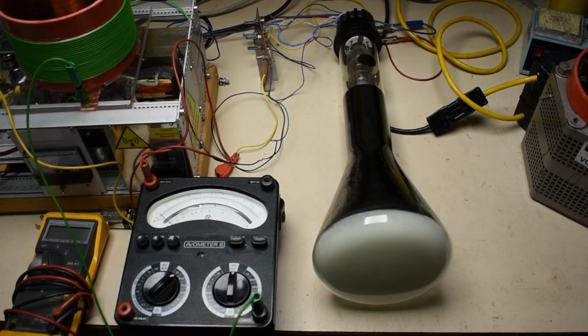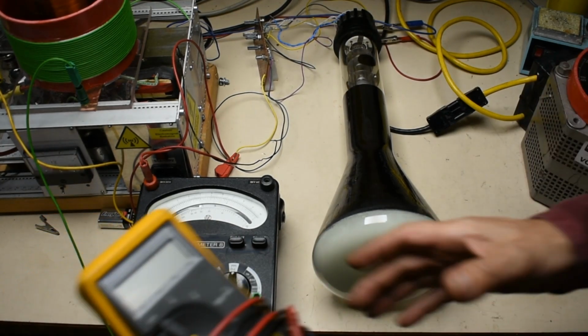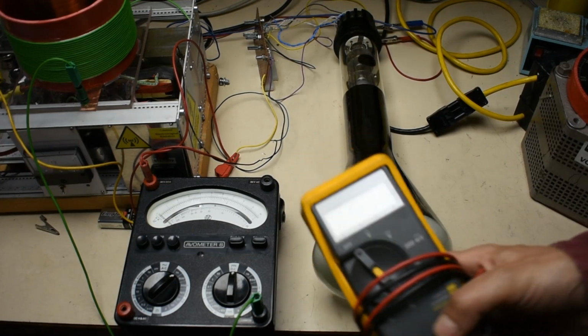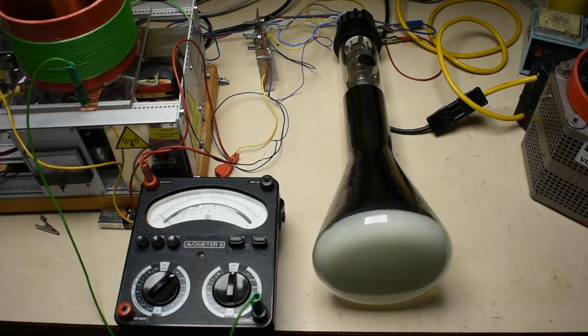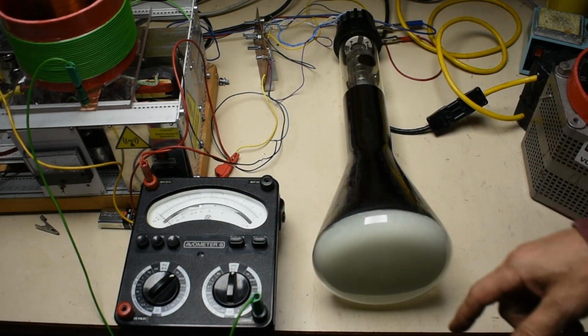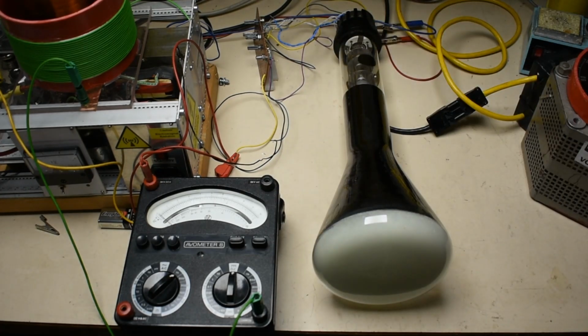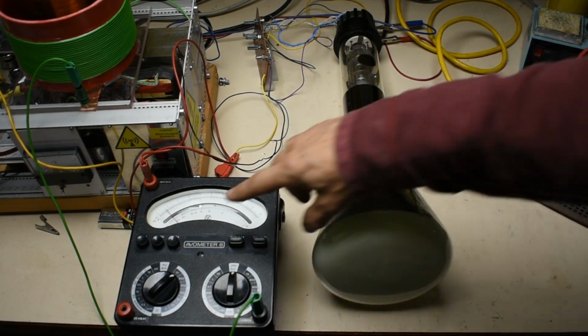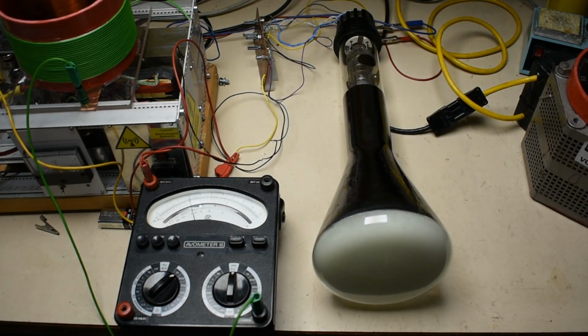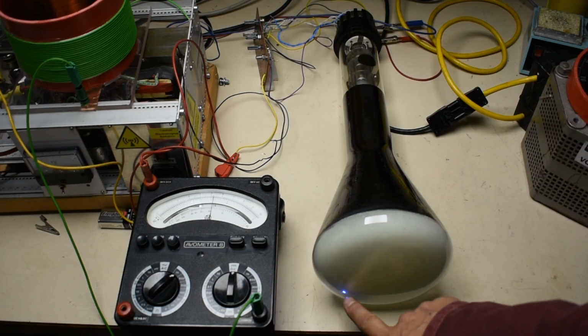One other point, if you're setting these up: these only go up to 1 kV, so you need an old-fashioned AVO meter to look at voltages above that, as I have set up here. I can bring up the voltage here, that's over 1K, or just around about 1K, that's 1.5, and you can see a blue dot has appeared on the CRT here.